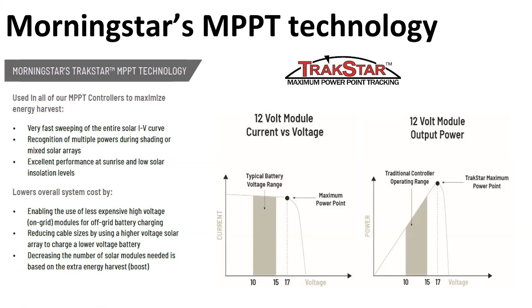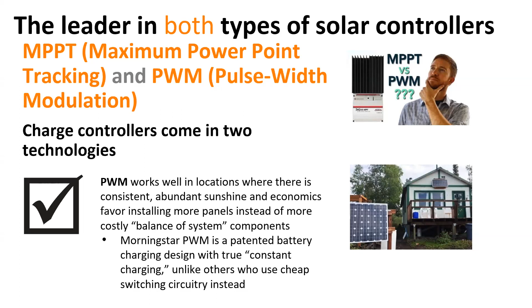To wrap it up, PWMs only operate at battery voltage, so you have to make sure your array is sized in accordance with your nominal system voltage. If it's a 48 volt battery system, you need a nominal 48 volt array, typically meaning two 72 cell modules in series. Similarly, for a 24 volt system, you may have one 72 cell module per string with parallel strings, or two 12 volt or 36 cell modules in series to equate to that 24 volt system voltage. Those are the types of constraints prevalent with PWM controllers that you're not necessarily subject to with MPPTs, so be aware of those differences.